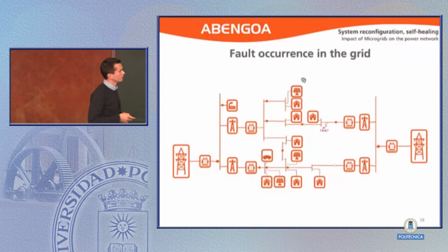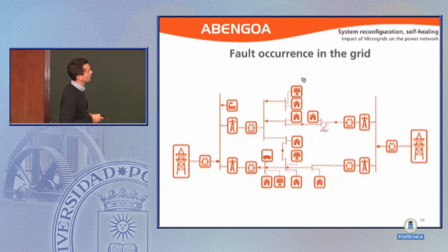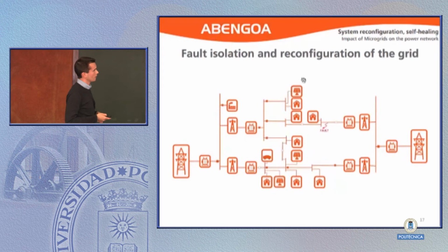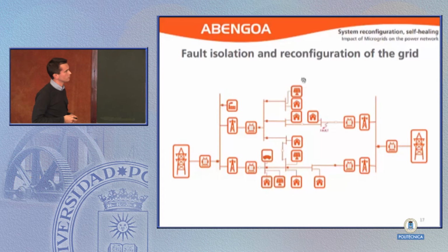For instance, here we have a power system, and the first section, the upper section, is fed through this transformer on the right, and we have the bottom section, which is fed with power through the transformer on the left. A fault occurs. This breaker senses the fault, and it will interrupt power flowing through this side, and these loads will be de-energized. When the fault location isolation and reconfiguration algorithm is being run, it has to take into account the constraints of the system. That is, the current limitations on the feeder, and also the power limitations of the transformer.